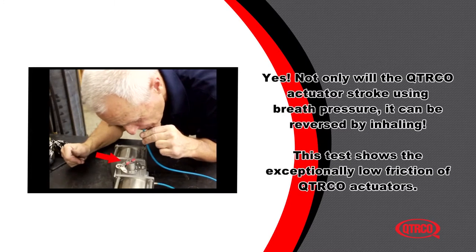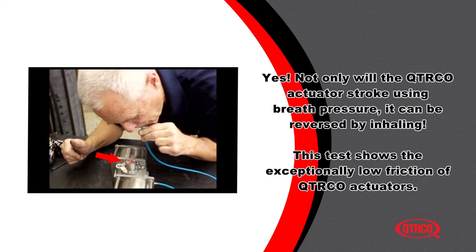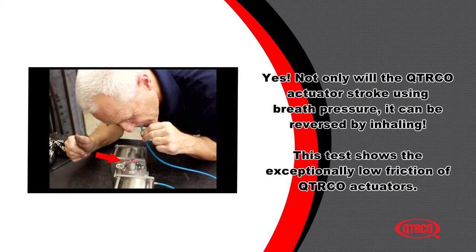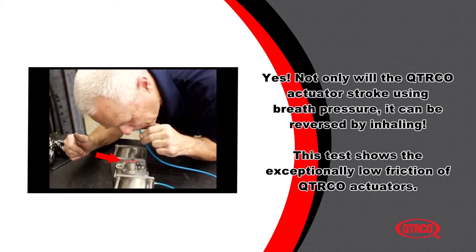Can we make the QTRCO actuator stroke by breathing into it? Yes, not only will the QTRCO actuator stroke using breath pressure, it can be reversed by inhaling. This test shows the exceptionally low friction of QTRCO actuators.